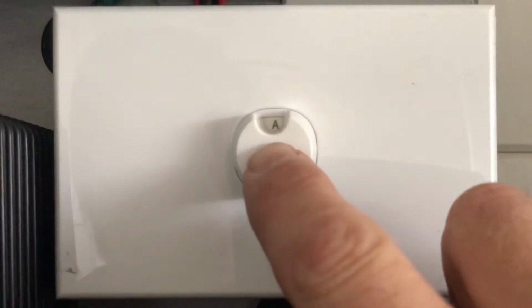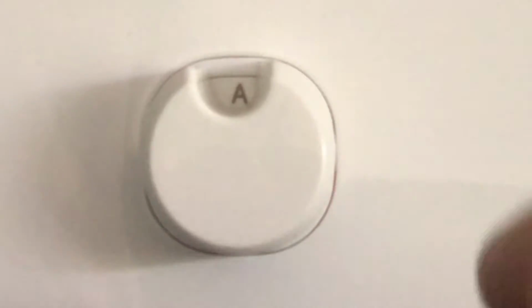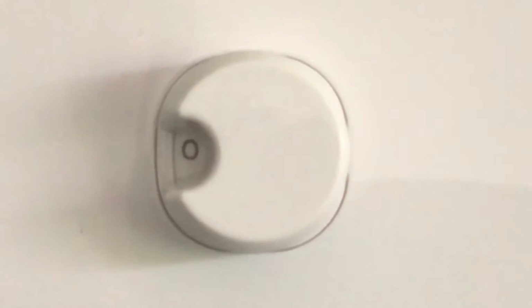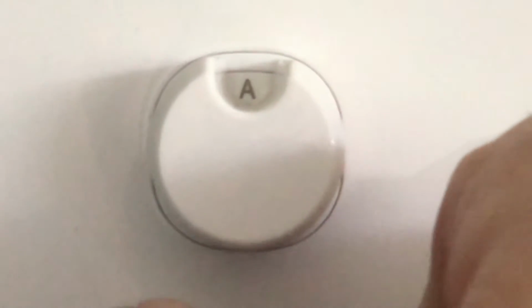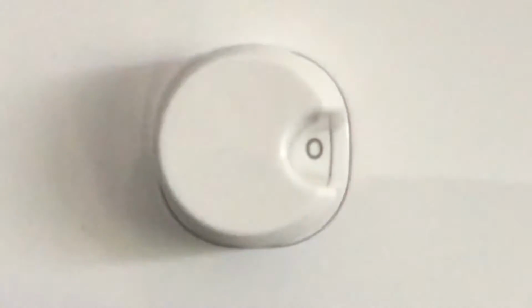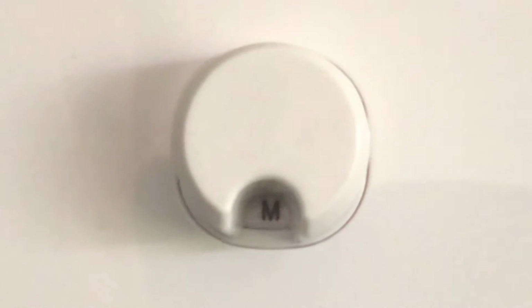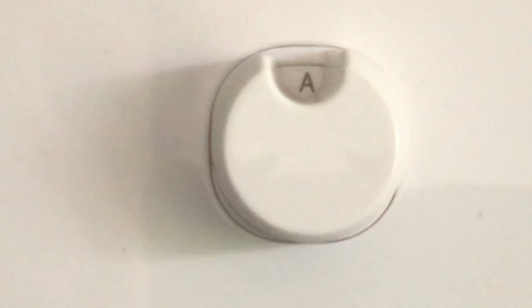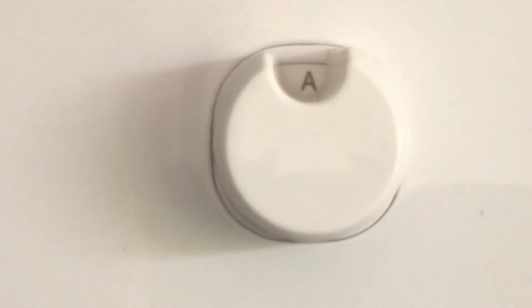So you can see the little A in the notch, and turning it to 0 either side. A is automatic, that means the system will start it when it needs to. 0 means it's off, it will not start. And M means it will start manually and turn the generator on, but remember to turn it back to off or auto when you've finished your manual run. There's not usually a reason you'd want to start it manually. The system should handle doing it automatic, unless you had a bad day perhaps and you wanted to get some energy back into the battery so the generator doesn't start at night time.